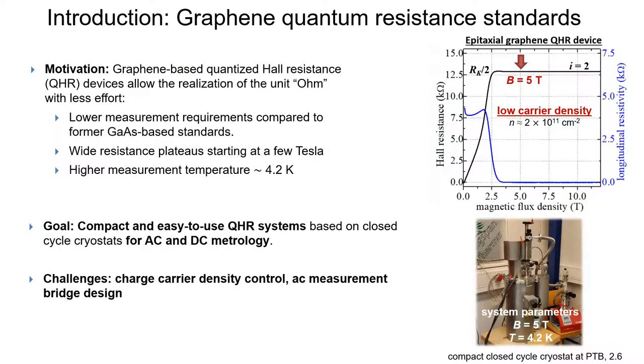The main motivation of graphene QHR devices is the realization of the unit ohm with less effort compared to gallium arsenide-based resistance standards. The goal is to use the advantages of the very broad resistance plateau and the higher measurement temperature to develop compact and easy-to-use QHR systems based on closed-cycle cryostats that operate not only at direct current but also at alternating current. Still challenging is the control of the charge carrier density of the graphene devices and the bridge design for measurements at alternating current. However, as you will learn in my talk and in those of my colleagues, we are making good progress in these points.